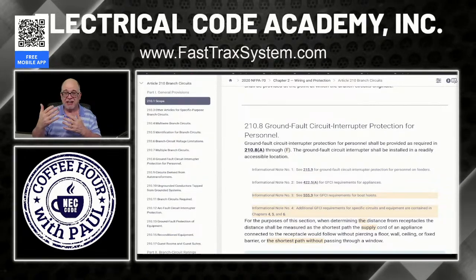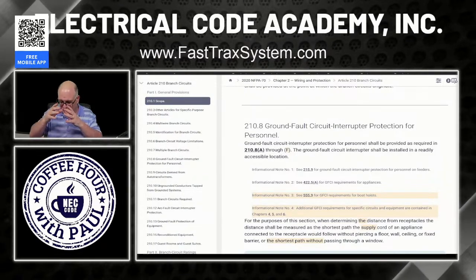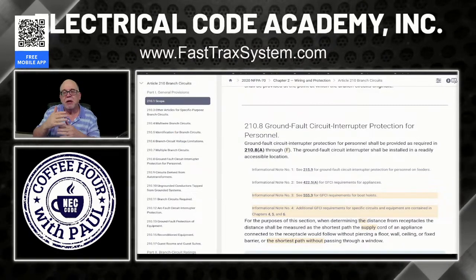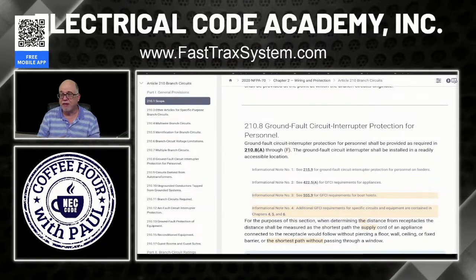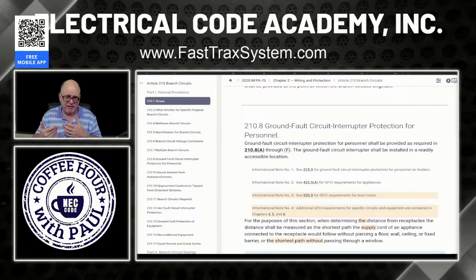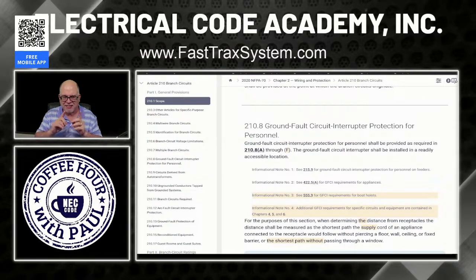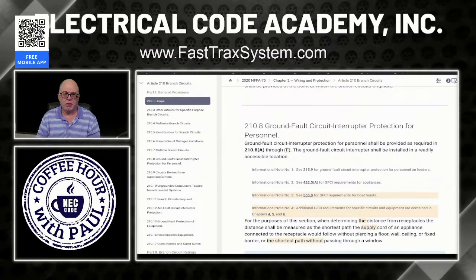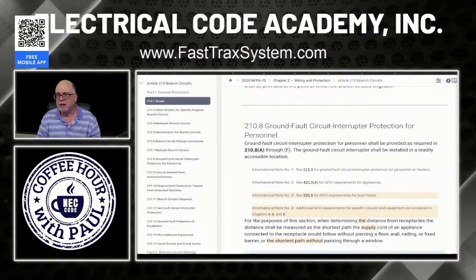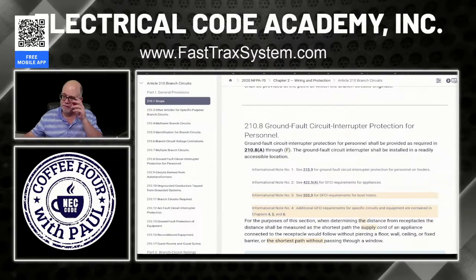That receptacle is, in theory, under the cabinet and not meeting the rules that we just read. But you can buy those that actually hardwire, and then they pop up above the countertop, or they flip up in the countertop, then those would be okay. That would meet this rule, and they're listed for that, okay? Just don't go buy the ones that have a cord on them with the attachment plug. Those are basically relocatable power taps, but they're designed in a way that they pop up and look all fancy. That's not the same. And you're going to know the difference by the price. The ones that you buy that are listed, that you hardwire, that are going to meet this rule, those are expensive, $300, $400, and $500 a piece, okay? So significantly more expensive. But they are listed for this application.